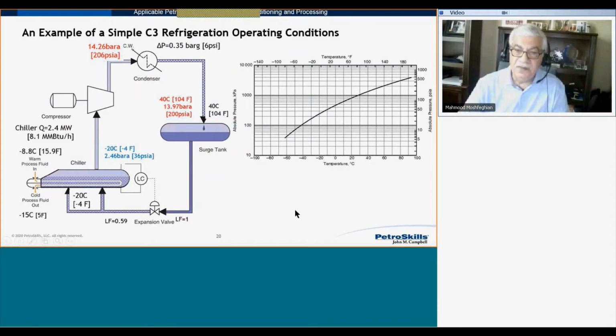Now let's see the concept as well. The chiller temperature is -20 degrees Celsius or -4 degrees Fahrenheit. So we identify that, we draw a vertical line, and we can read the chiller pressure at this temperature. On the left-hand side is kilopascal. On the right-hand side is FPS unit.